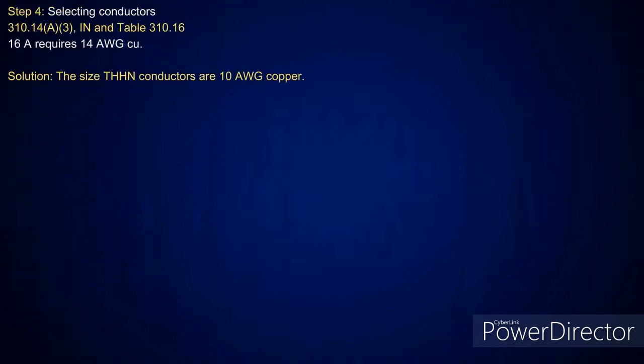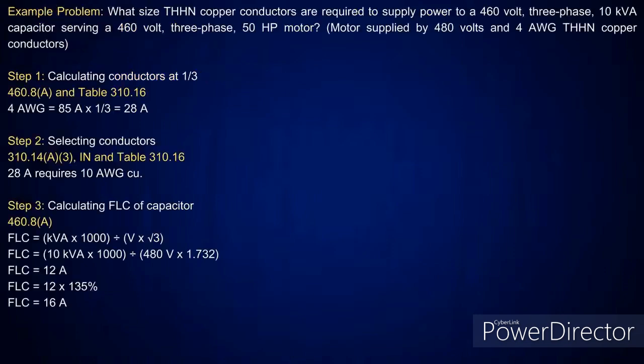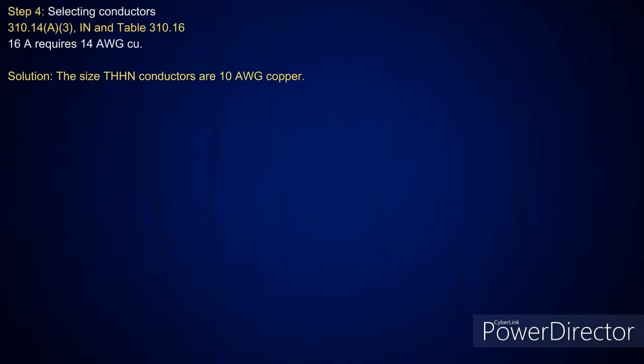Now, as you go in the second part of it, number 16 is going to require number 14. But you have to use the largest between the two. Well, you're saying 16 amps requires a 14. But if I look at, so you're going off the 75-degree C column, right? Yeah. Okay. And then when you come here and you look, which was the largest between the two? Well, it's where I calculated the conductors at a third. Okay. Gotcha. So therefore, the answer for this particular one going over to that capacitor is going to require me to have number 10 copper conductors.